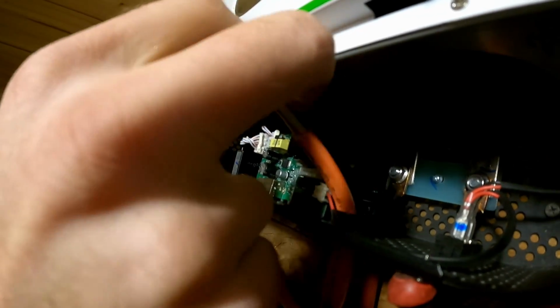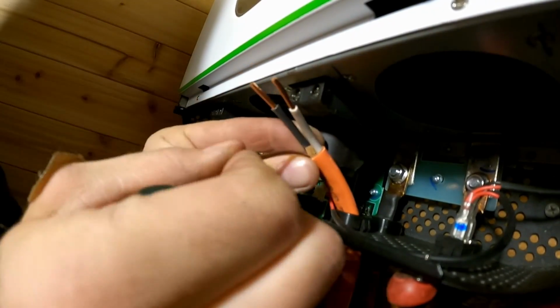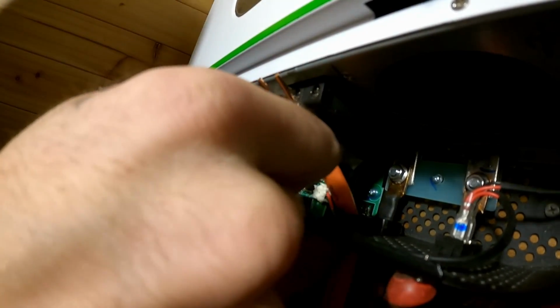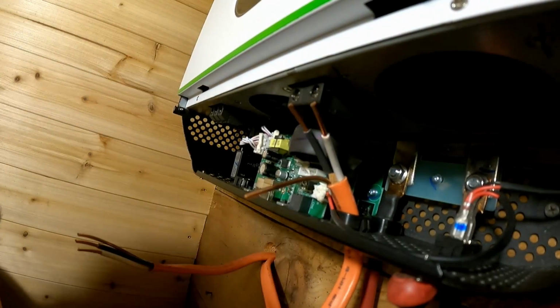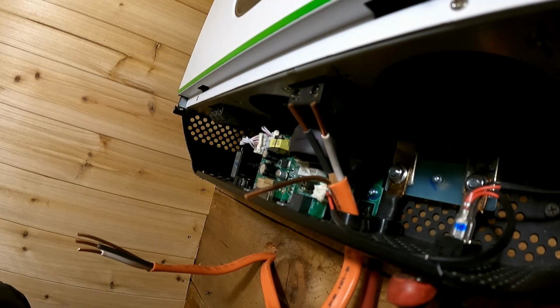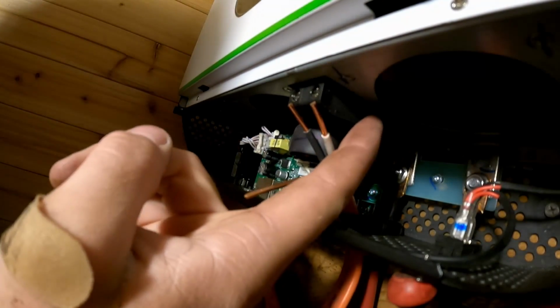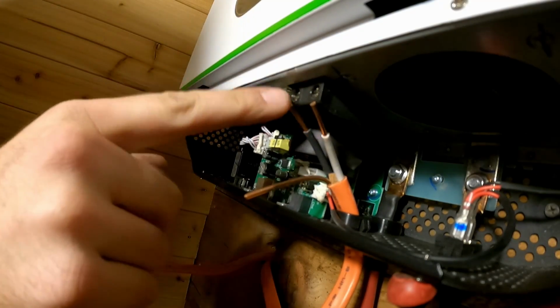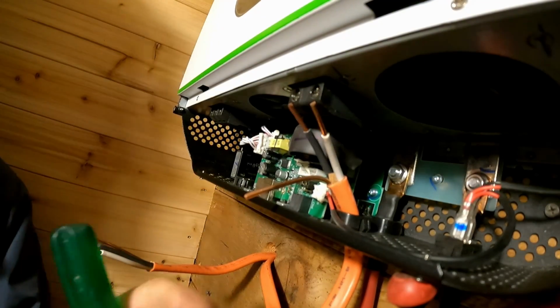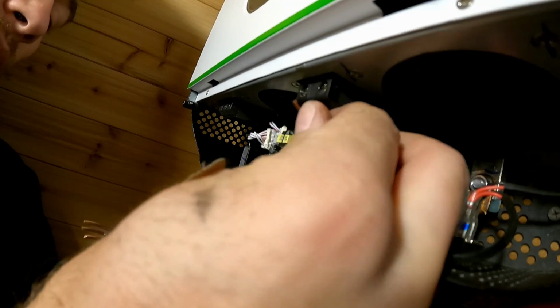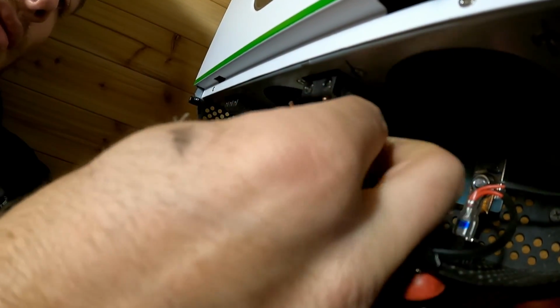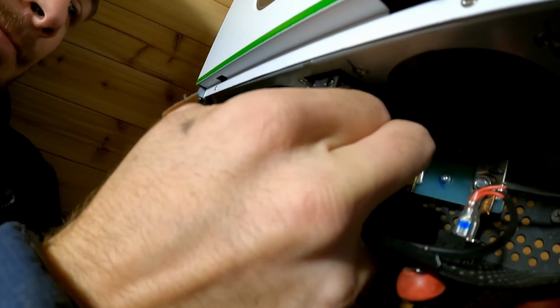The solar only has two leads and no ground, so I'll bend the ground out of the way. Underneath there's a legend: this side is PV minus, this side is PV plus. I'll run black to PV plus and white to PV minus.